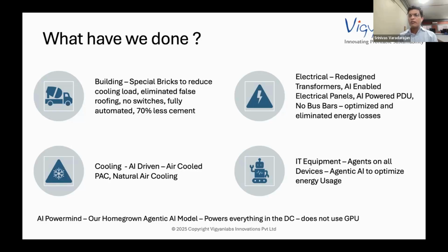We had to work with the chiller vendors and ask them to give us the APIs. We said, why can't we use AI? We built an AI-based closed loop control system that controls the chiller in real time, based on server load and thermal footprint. Using that automation, we were able to reduce the PUE from 2.0 to less than 1.3. So that automation of the chiller helped us.